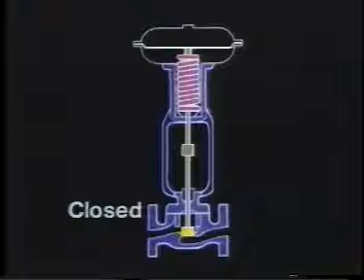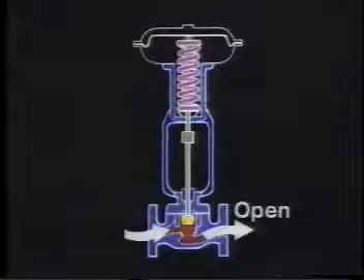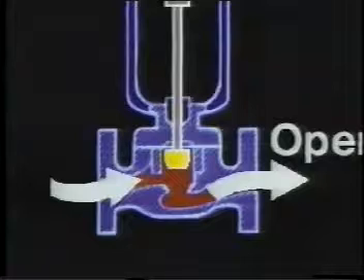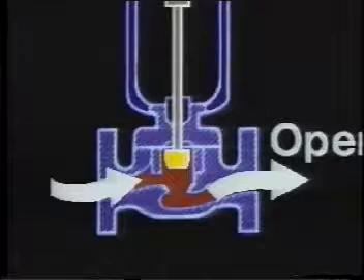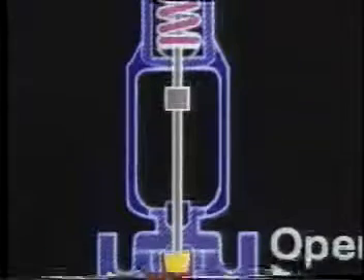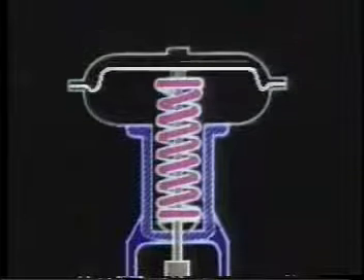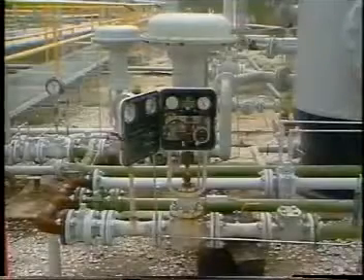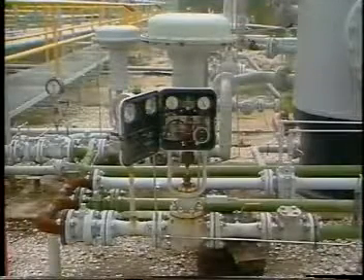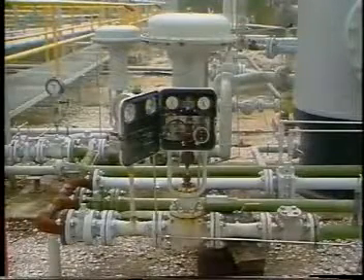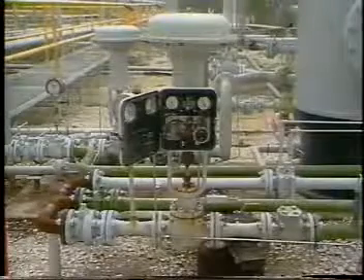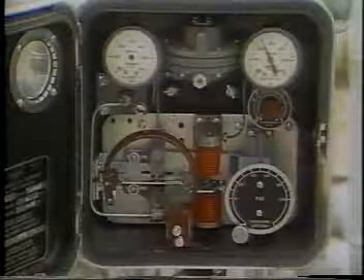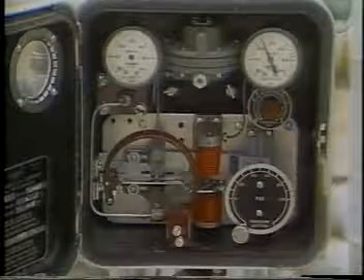The valve orifice is adjusted larger by moving the valve stem upward, moving the plug off the valve seat, and creating a larger area for flow. The pneumatic actuator diaphragm is supplied with compressed air or gas, which overcomes the spring resistance and moves the stem upward or downward. The pressure controller senses the pressure in the vapor space of the pressure vessel or tank and regulates the control valve. By regulating the amount of gas leaving the vapor space, the desired pressure in the vessel can be maintained.